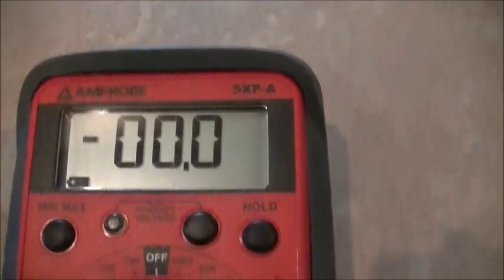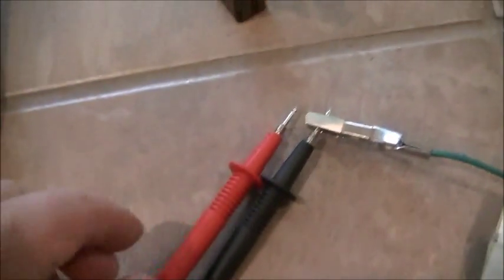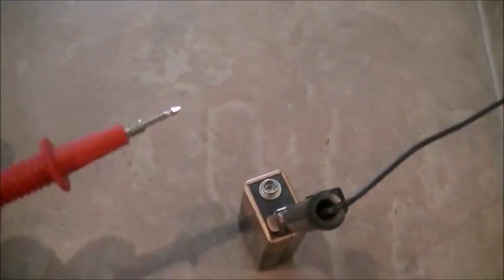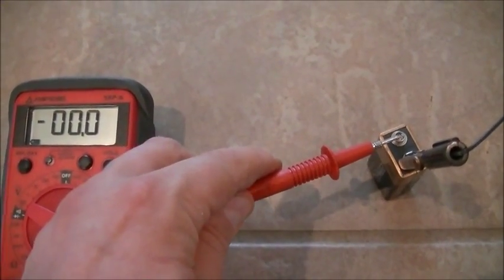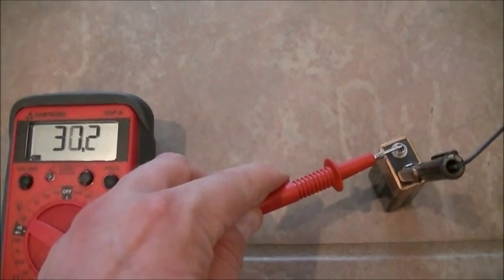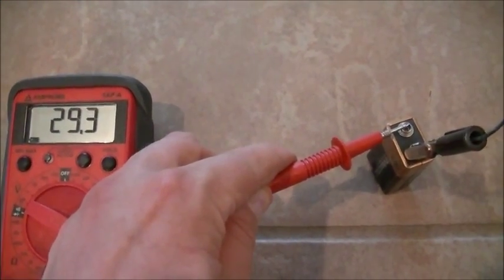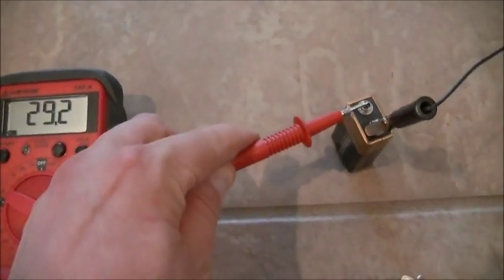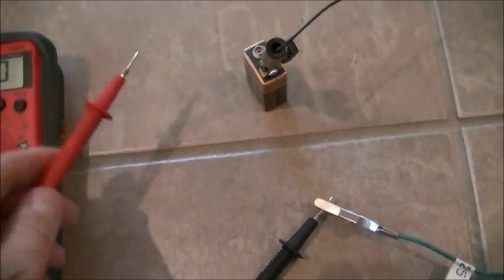We're going to put our multimeter on DC amps 200 milliamps and use the red probe to complete the circuit. I'm going to pull this back so you can see both the meter and the battery. When we connect to the battery, you get approximately 30 milliamps flowing around the grounding circuits. That means we have a very good connection.